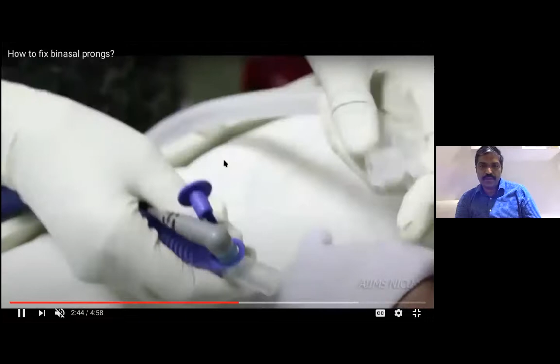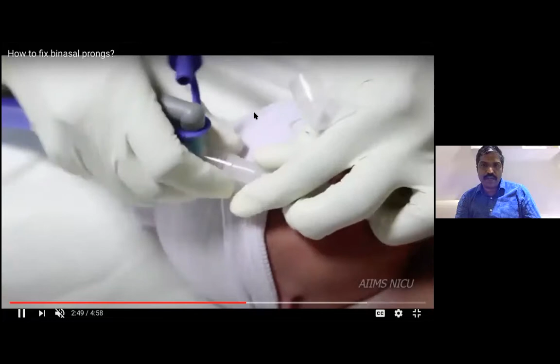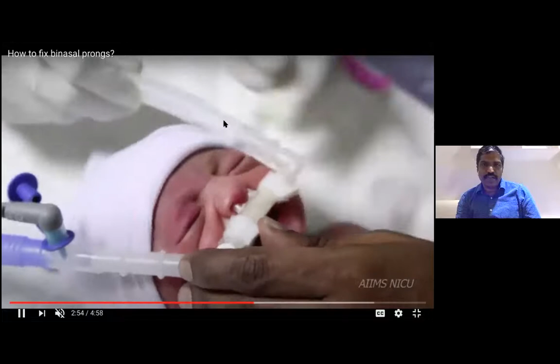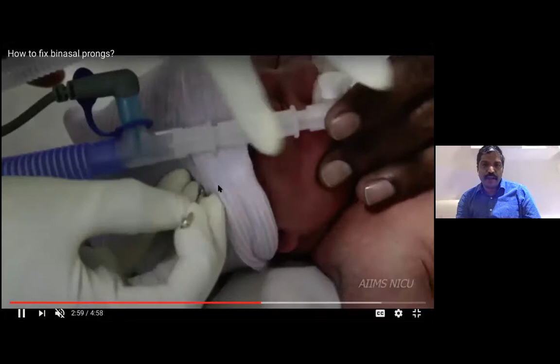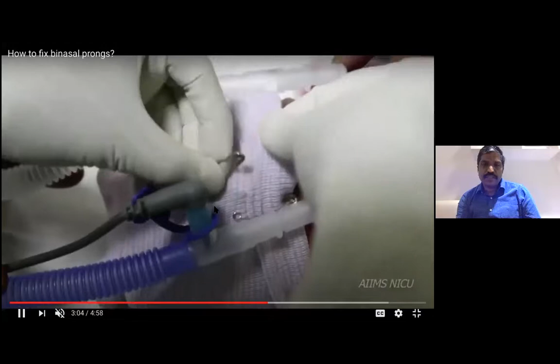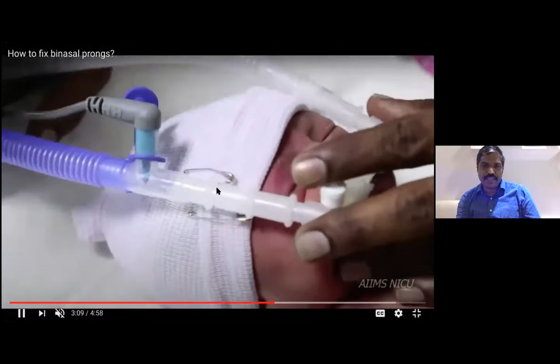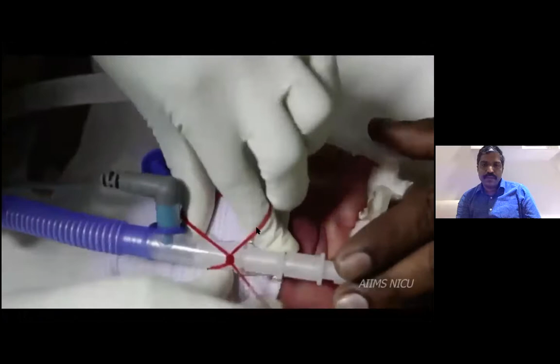Now you fix the inspiratory limb to one end, and the expiratory limb to the other side. So the blue is connected to one side, the white is connected to the other side. Now you have to fix these interfaces to the cap, and for that you use the safety pins. So first fix the interface and then fix the interface to the cap so that they stay in one place. Make a Y of the rubber band and then fix the interface to the cap.